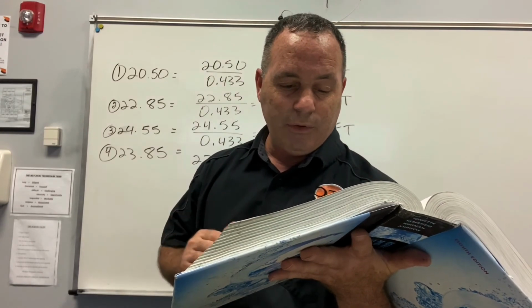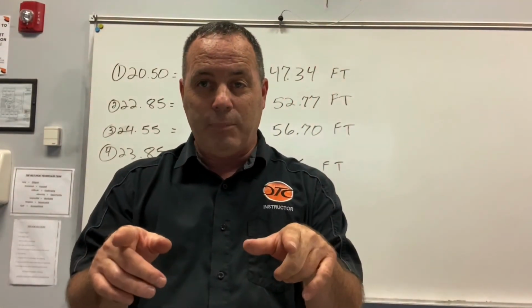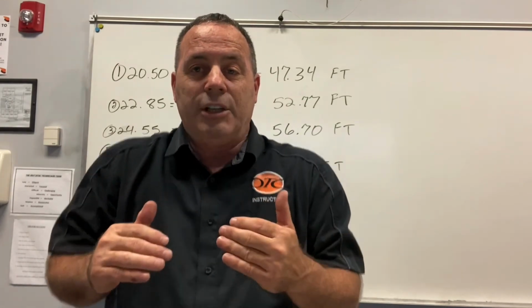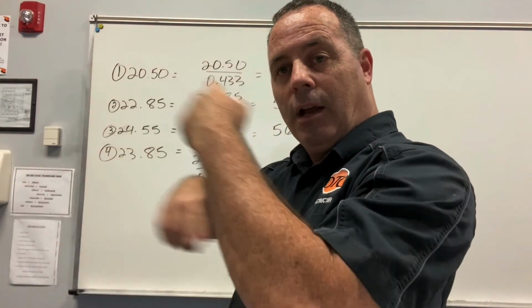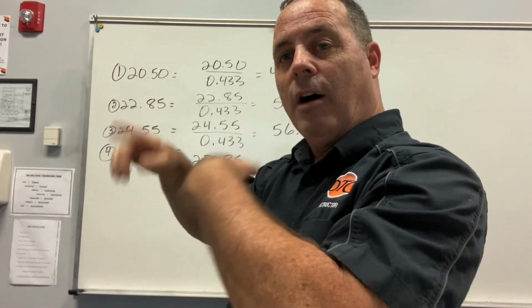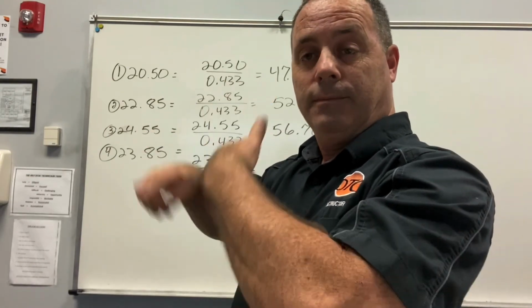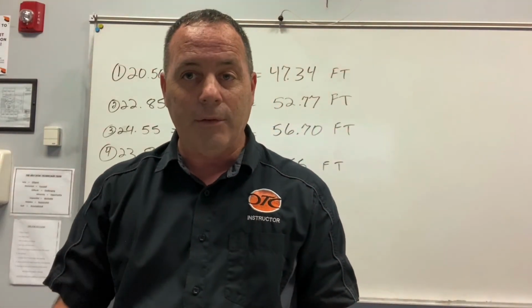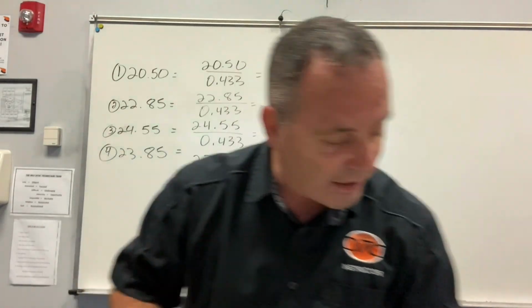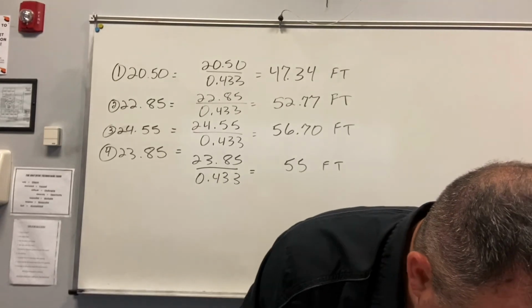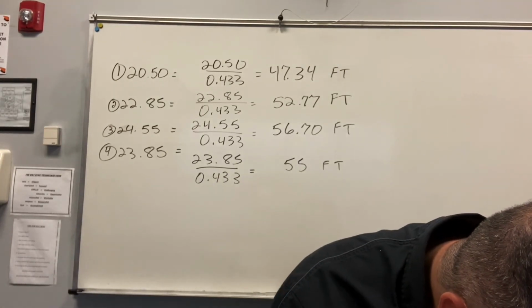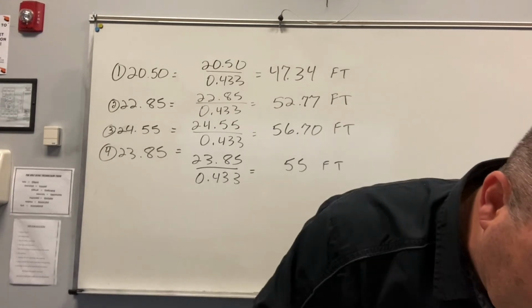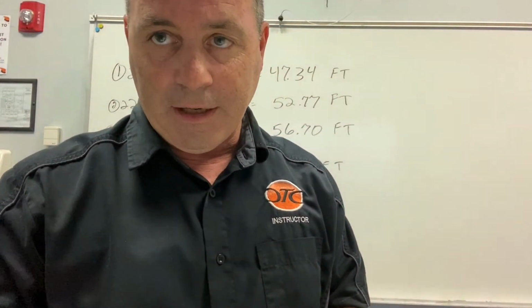This might sound counterintuitive. When a valve is installed in the piping circuit and it's closed, it would seem it would create a greater rise in pressure to increase the head pressure against it. But it doesn't, because it's a water circulating pump. It's not a compression pump. So the water is creating a pressure difference, and when you cut the valve off, it just sits there churning in the water. So notice the amps went down, and then there was no water movement. So that's what's going on in that page right there, okay? Now, let's go on to the differences on page 981 of the different parts.